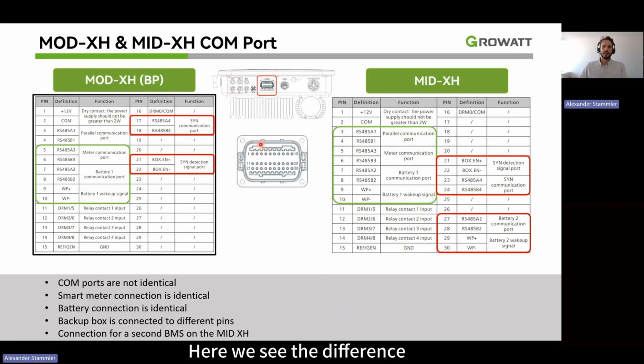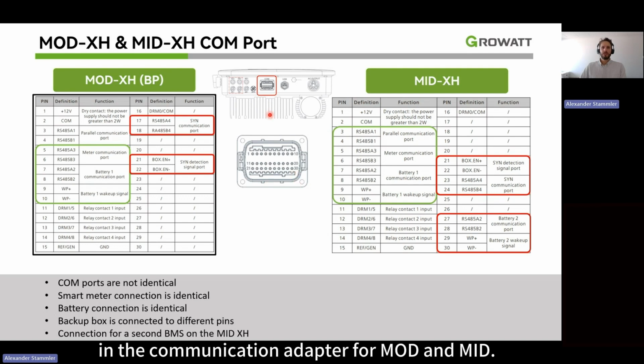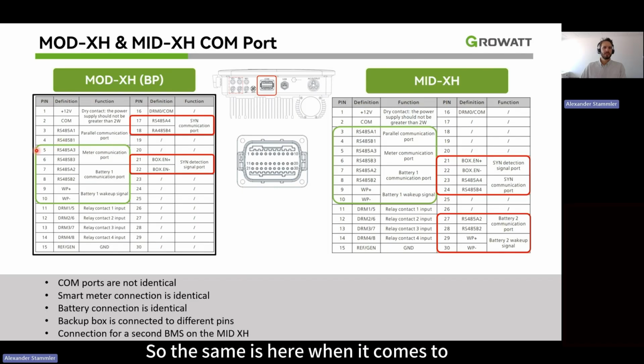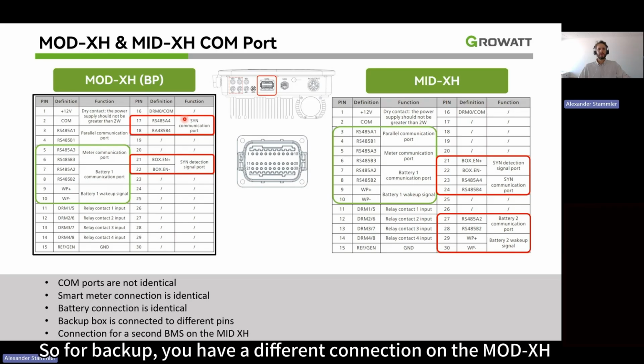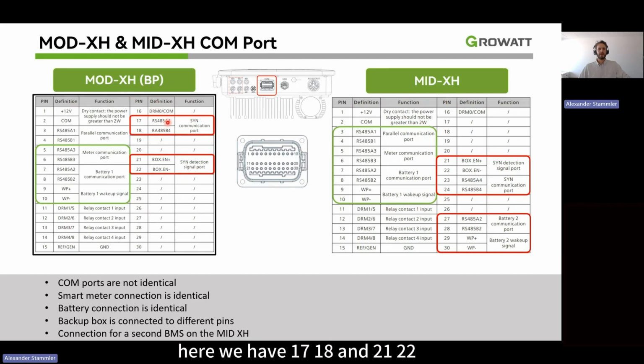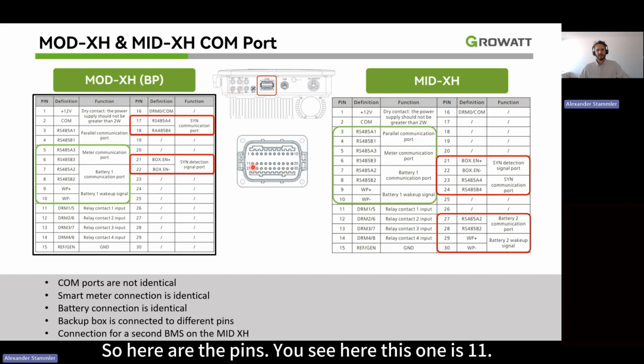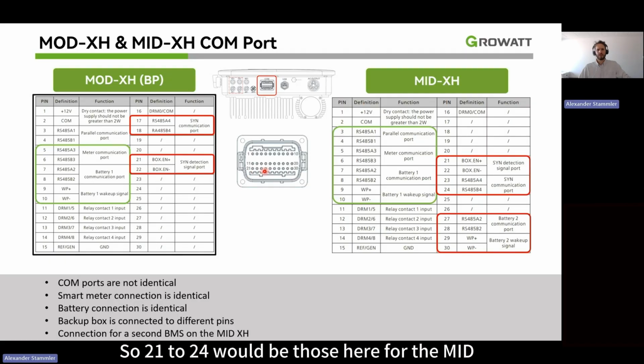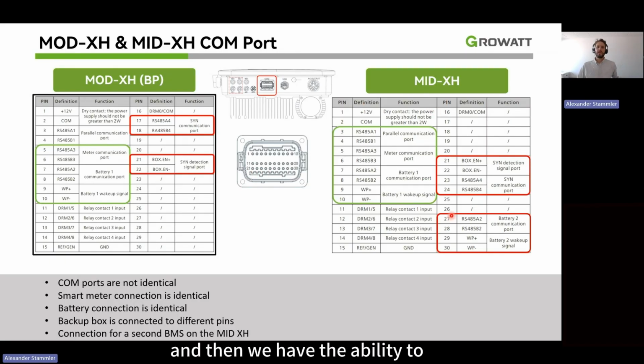Here we see the difference in the communication adapter for MOD and MID. The same is true here when it comes to the smart meter connection and the first battery pack. They're the same. And then the SYN box, so for backup, you have a different connection on the MOD XH. Here we have 17, 18 and 21, 22. And the MID XH has 21 to 24. So here are the pins. You see here, this one is 11. Here we have 20. So 21 to 24 would be those here for the MID. And then we have the ability to connect the second battery pack or cluster on the pins 27 to 30.